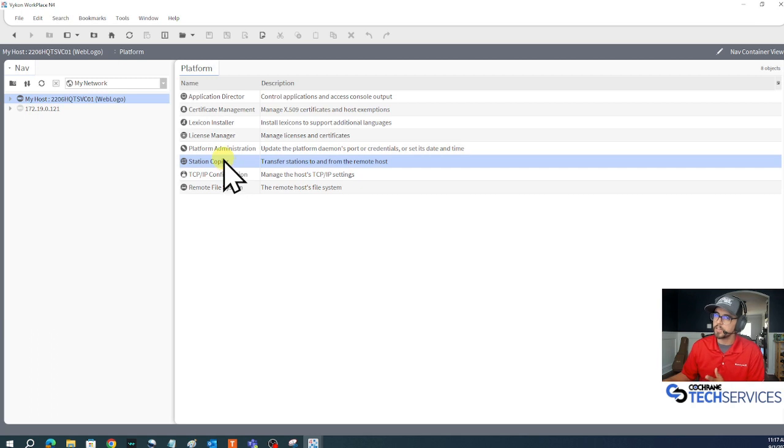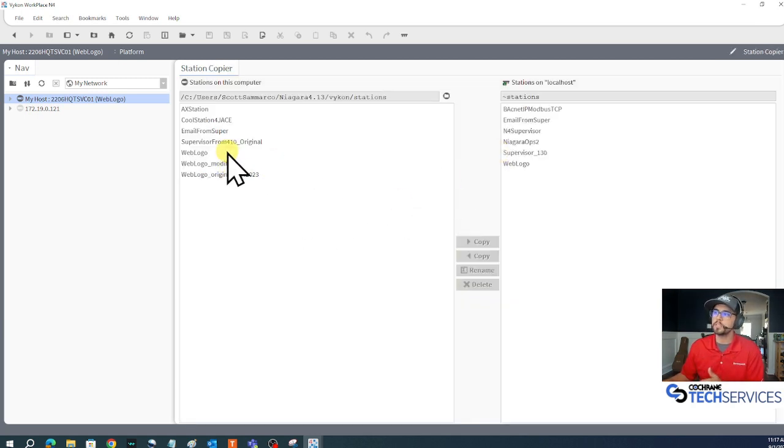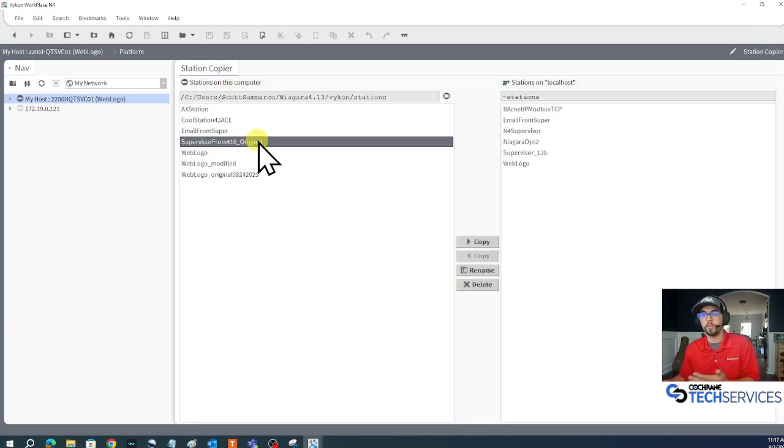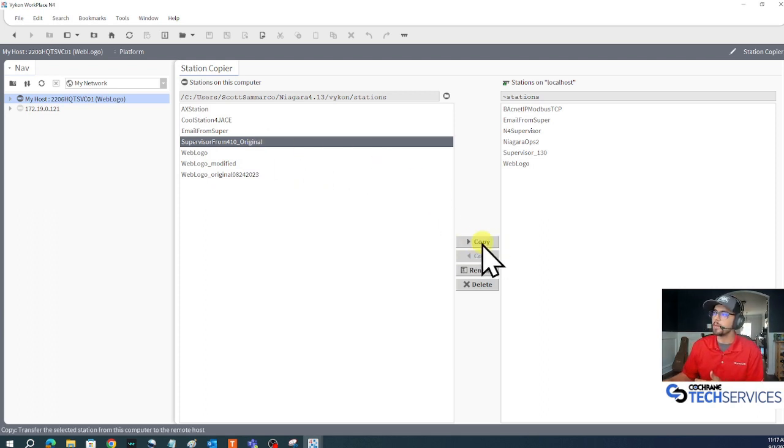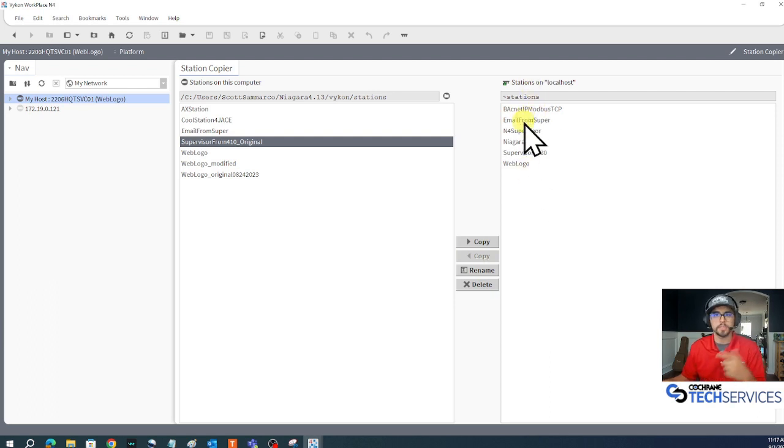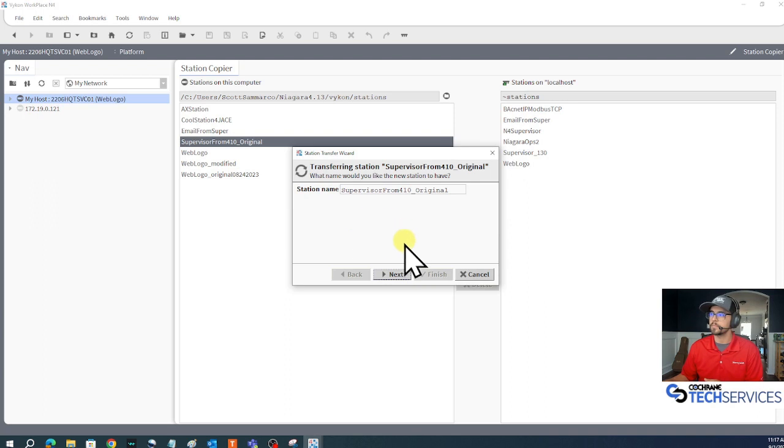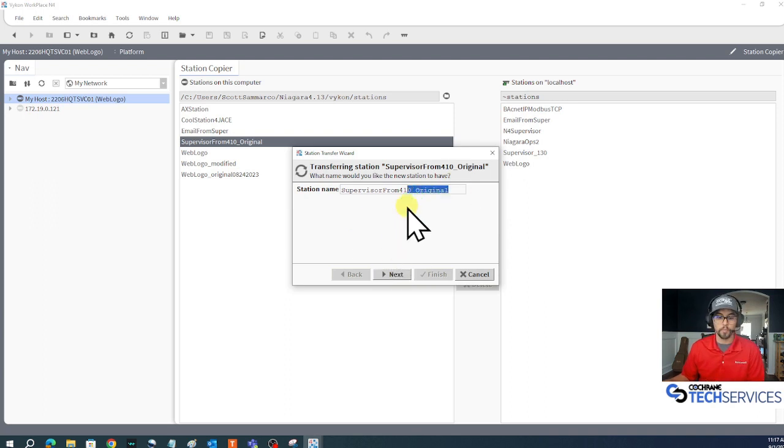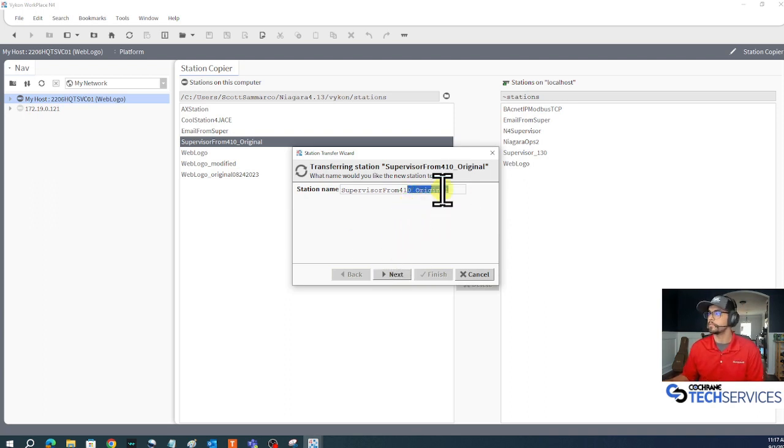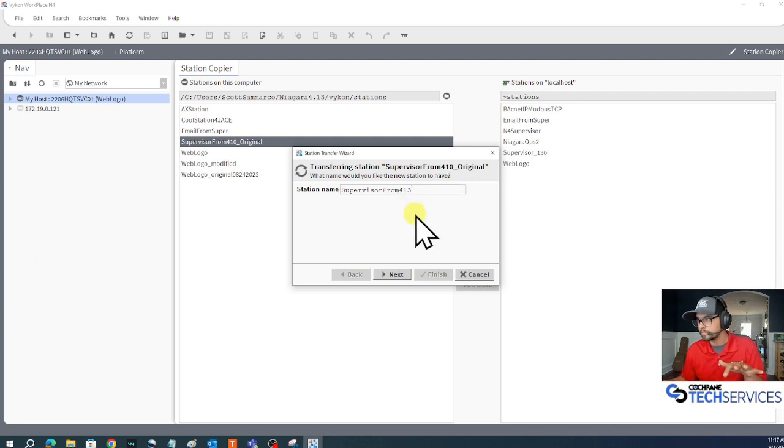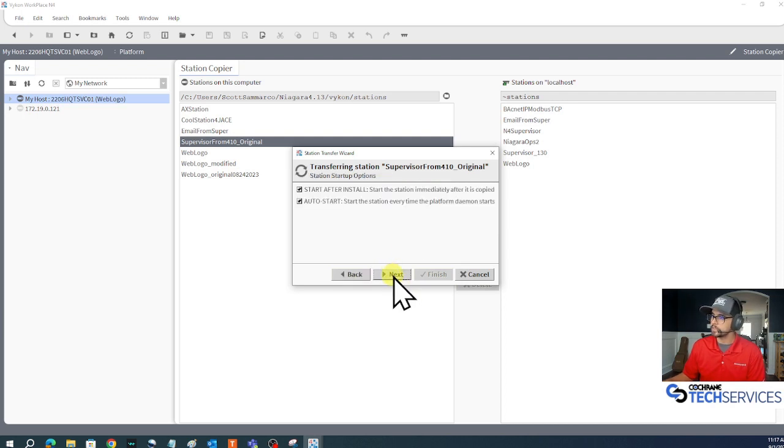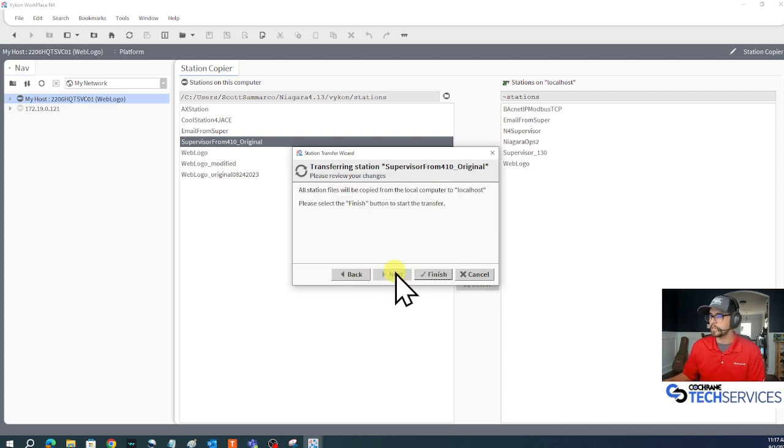Here's my station copier of my platform and what I'm going to do is take this supervisor from 4.10 original and copy it over to my 4.13 daemon home. Notice the stations have changed because the daemon that's running has changed. Click my copy button, maybe I'll say 4.13, press the wrong button, click next, start after install is fine, click next and finish.